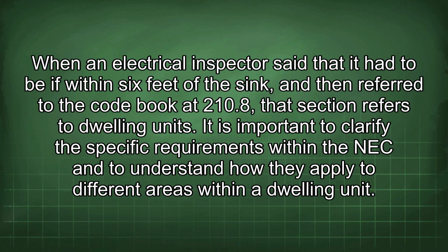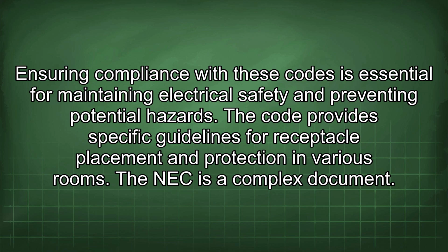When an electrical inspector said that it had to be within 6 feet of the sink and then referred to the code book at 210.8, that section refers to dwelling units. It is important to clarify the specific requirements within the NEC and to understand how they apply to different areas within a dwelling unit. Ensuring compliance with these codes is essential for maintaining electrical safety and preventing potential hazards. The code provides specific guidelines for receptacle placement and protection in various rooms.